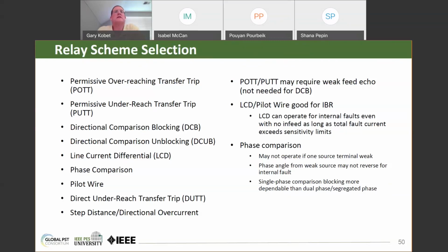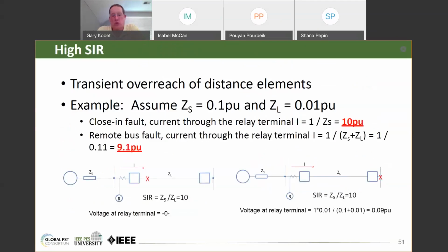The next slide talks about high source impedance ratio, and this is a sample system. The idea here is that if you have a very high source to line impedance ratio, for internal and external faults, there may not be enough difference between the fault currents for an internal and external fault for the relay to discriminate between the two. In the sample here, the difference is less than 10%, for an external bus fault and an internal fault, the difference is only less than 10%.